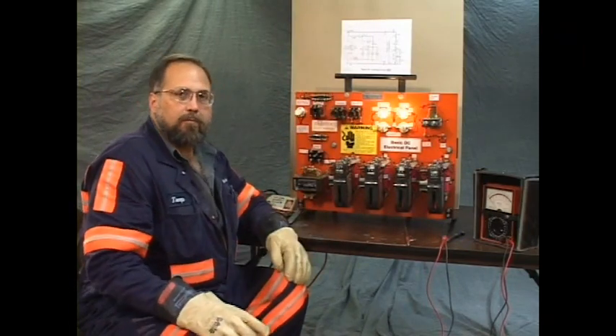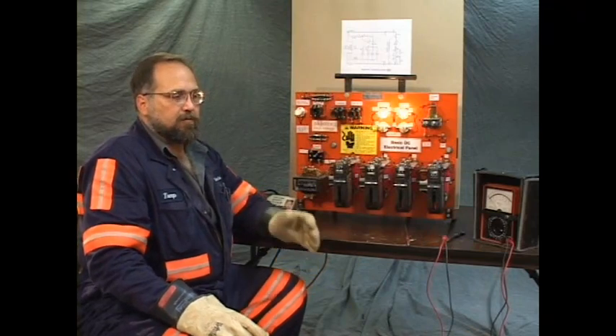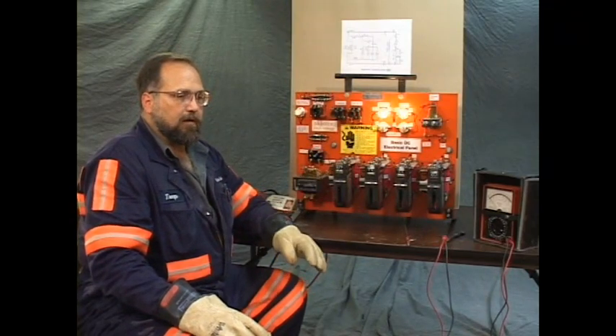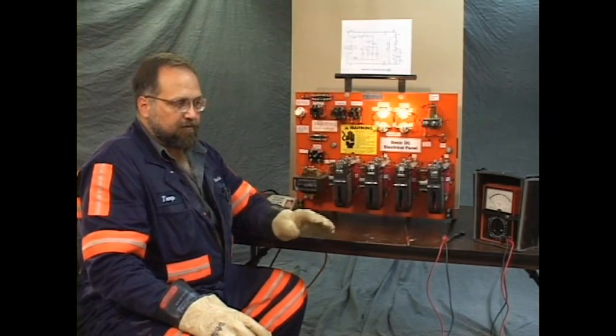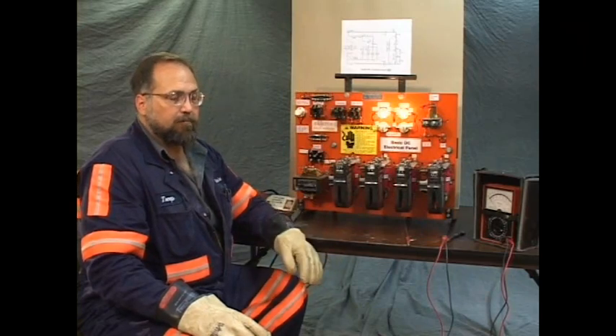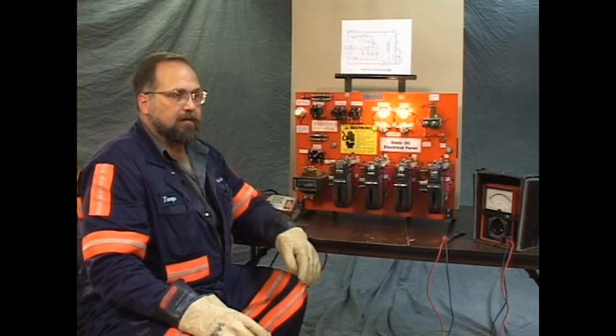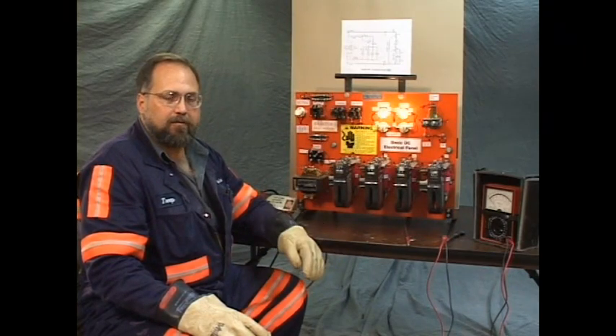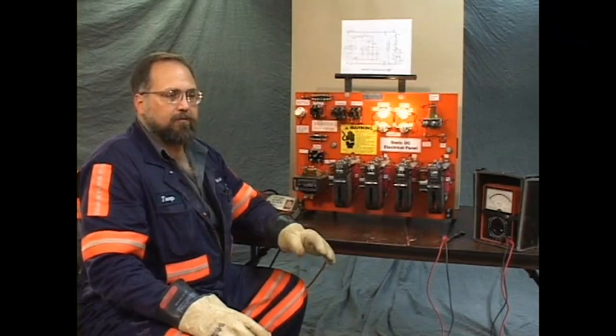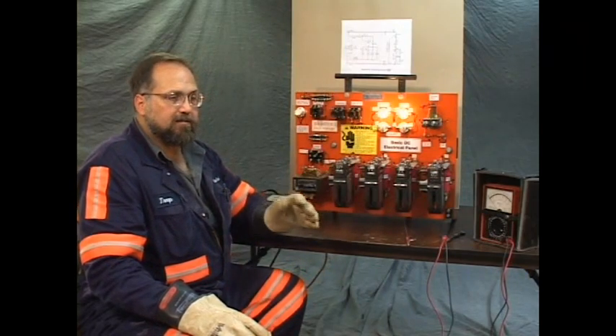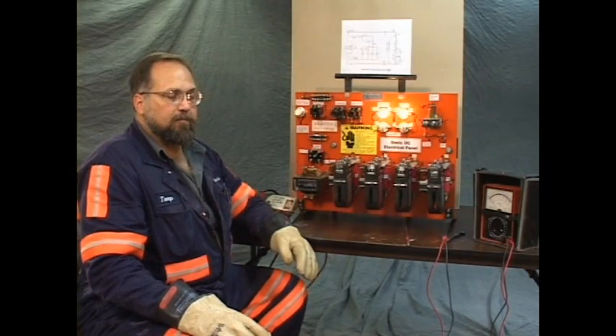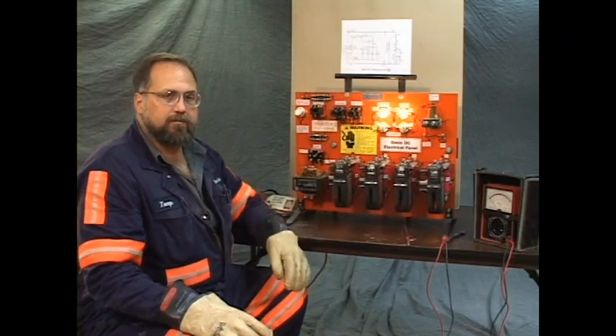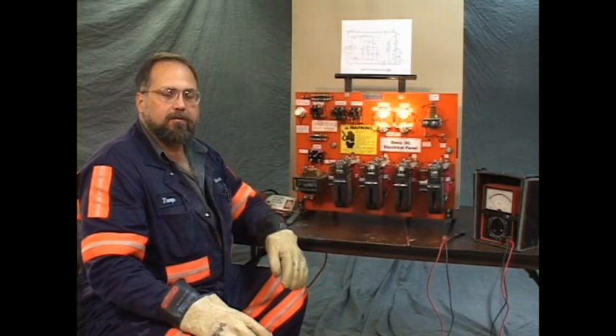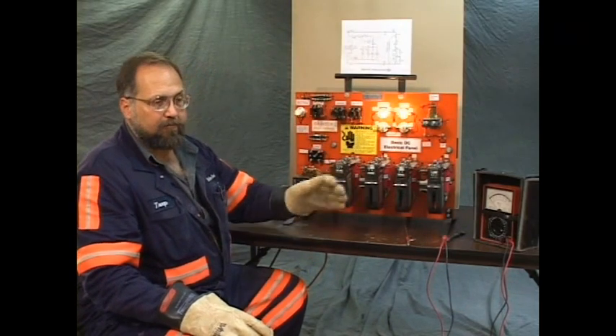If this were on a motor, on a piece of equipment, say it was a traction motor, when the operator depressed the tram pedal to go, nothing would happen. He would hear the clicks in the panel. And then when it cycled through the control to the high speed, then the piece of equipment would start with a lurch. It would jerk from 0 to high tram.